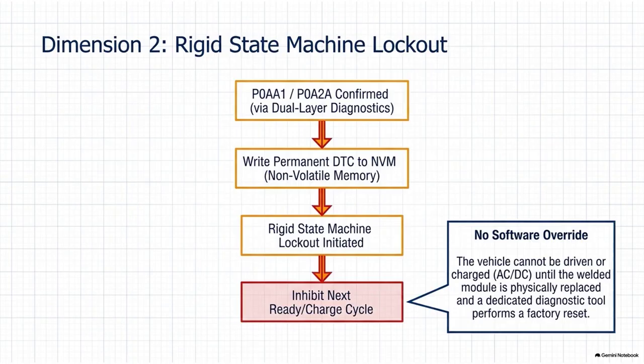Exactly. And most importantly, it prevents a high-voltage charging station from pumping massive thermal energy into a battery pack that has lost its physical ability to stop the charging process and protect itself from overcharging and thermal runaway. I deeply respect the absolute ruthlessness of that software logic. You are not safe, therefore you are not moving, and you are not charging, period. That's the ASIL-D mentality. But as I was reading through the engineering use cases, I found a scenario where that thoughtful, deliberate software logic is completely useless.